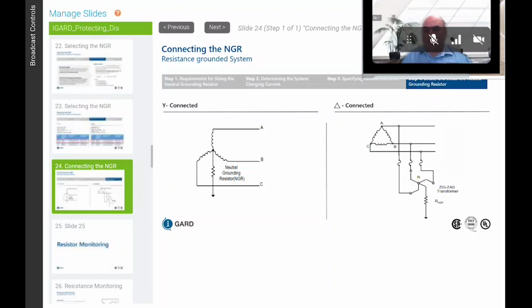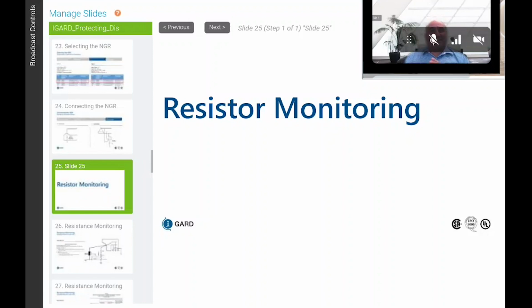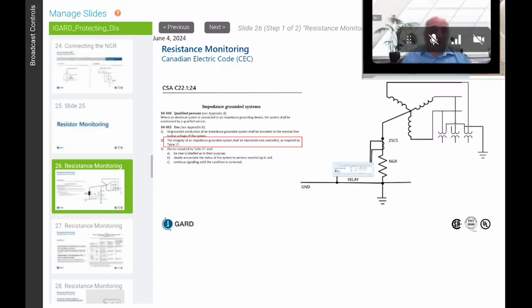Conversely, if you don't want to use a zigzag transformer, you can use a Y-grounded delta or a Y-grounded open corner delta. And if you're as old as I am, you'll know what a Y-grounded open corner delta is. So we get into resistor monitoring. In Canada, under CSA M421 for the past 30 years, we have had to have resistor monitoring in the mining sector, and it's been recently adopted into the Canadian Electrical Code, where every resistance grounding system has to have the resistor monitored to make sure that it's in the circuit, because if it's not in the circuit, we can quickly change the system to a solidly grounded system or an ungrounded system if something happens to the resistor, and we can discuss that.